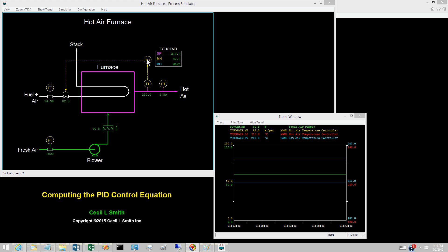And if the modes were computed individually and summed to obtain the controller output, surely someone would have come up with the bright idea of displaying the outputs of the individual modes. The computation sequence presented in this video follows the approach used in conventional analog controllers. However, there is a fundamental difference: the analog controllers solve differential equations, while digital controls require difference equations.